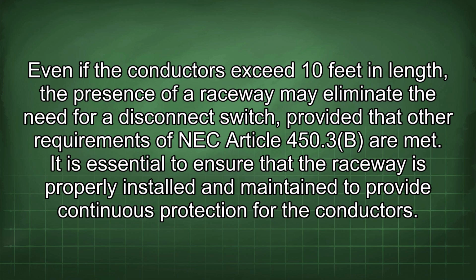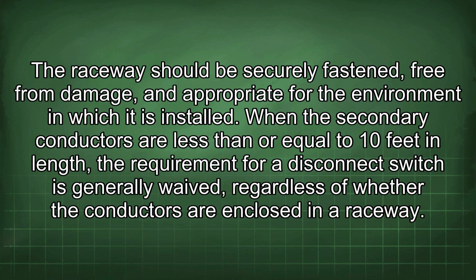It is essential to ensure that the raceway is properly installed and maintained to provide continuous protection for the conductors. The raceway should be securely fastened, free from damage, and appropriate for the environment in which it is installed. When the secondary conductors are less than or equal to 10 feet in length, the requirement for a disconnect switch is generally waived, regardless of whether the conductors are enclosed in a raceway.